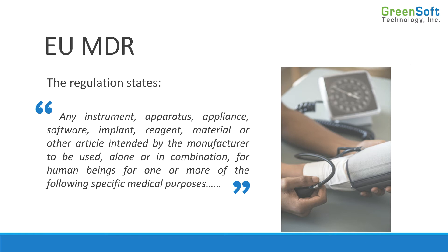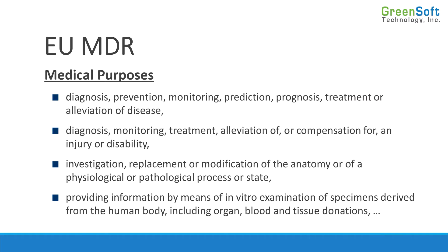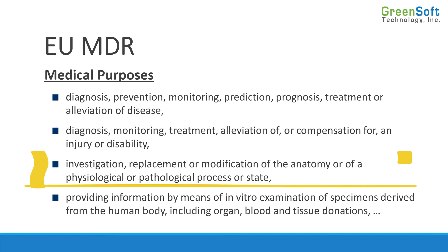Notice it says for human beings, not for animals. So veterinarian equipment is not a medical device. Now going through this list, it's pretty simple when it talks about diagnosing or treating a disease or disability. When it talks about investigation, replacement, or modification of the anatomy or of a physiological or pathological process or state, what it's saying is that if we have some device that messes with our heart rate — like a pacemaker — that changes the pathological or physiological process or state. So even though it may not treat a disease or an injury, if we have something that's messing with how our body works, that's a medical device. The same goes for any kind of limb replacement — that would also be considered a medical device.